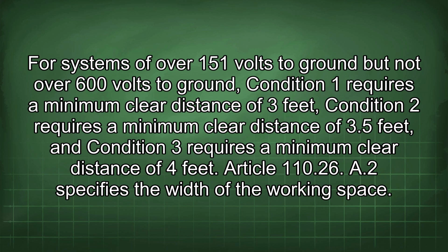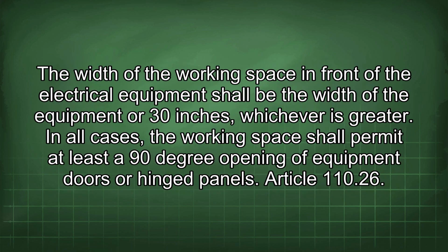Article 110.26 A2 specifies the width of the working space. The width of the working space in front of the electrical equipment shall be the width of the equipment or 30 inches, whichever is greater. In all cases, the working space shall permit at least a 90-degree opening of equipment doors or hinged panels.